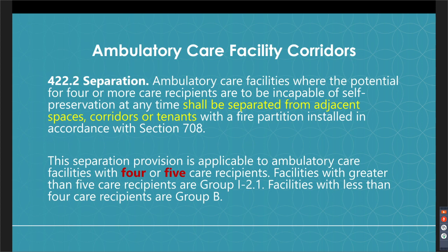So you can see the section changed here, 422.2. Still in Chapter 4 for those special uses, but 422 is for ambulatory care facilities. You'll see similar language here. If you've got an ambulatory care facility, you would go to this section, but there's still a requirement for the separation of spaces. The corridor space has to be separated with fire partitions in accordance with 708, and spaces adjacent to the tenant spaces also have to have separation from those other tenant spaces with the 1 hour fire partition. Again, this is just fresh in the memory, your ambulatory care facilities with 4 or 5 care recipients. If they've got more than that, then you go to the I-2 requirements in 407 that we just talked about.